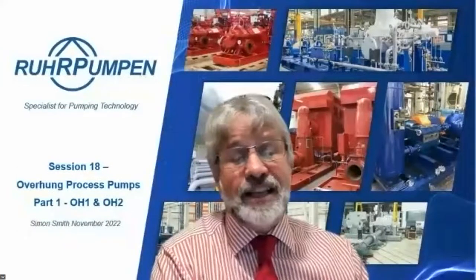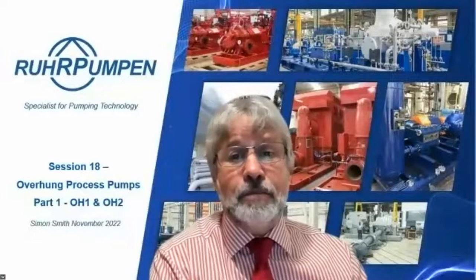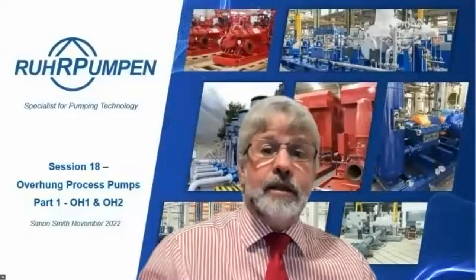Ali Al-Fatal says, for a high temperature and severe chemical impact at the same time, what is our best option? Thank you, it was a great lecture. Well, thank you for that comment. High temperature and severe chemical impact. Again, high temperature, immediately you have to be API 610. And API 610 does have strong material options. It will allow you, for example, to have a duplex or a super duplex pump, or 316 stainless. Those are standard materials within the API 610 remit.